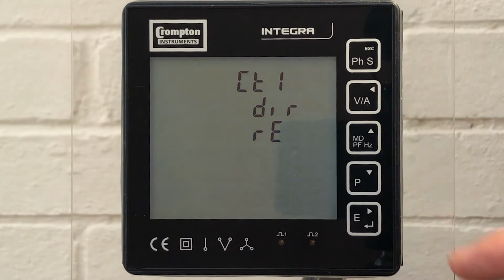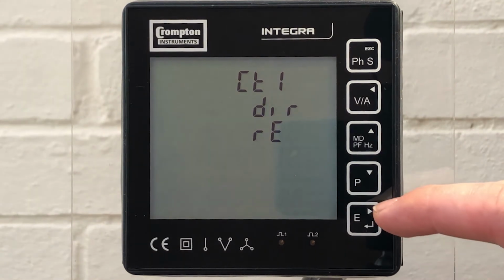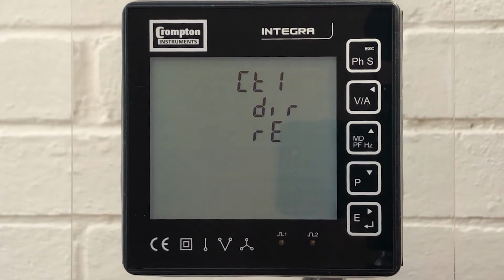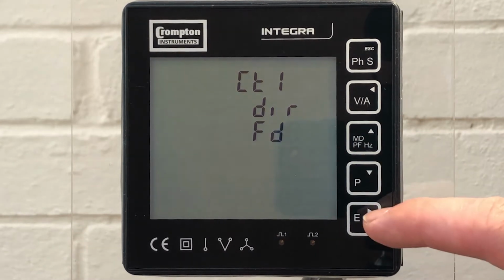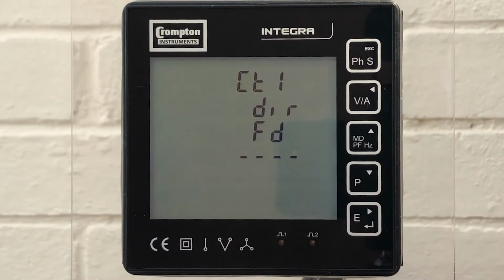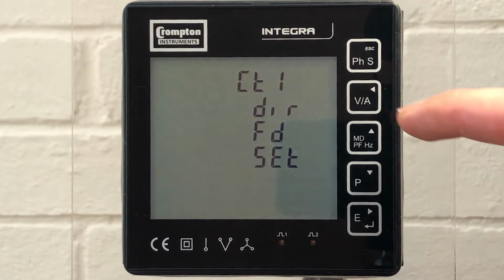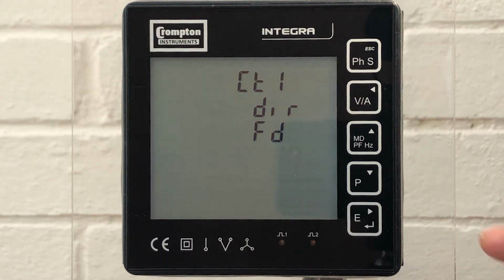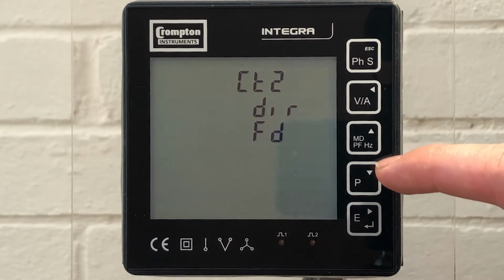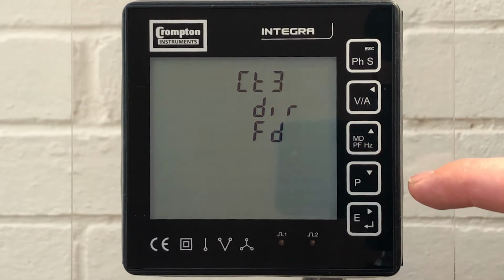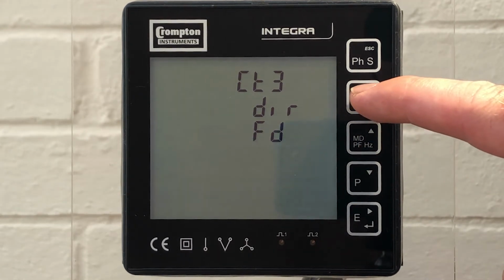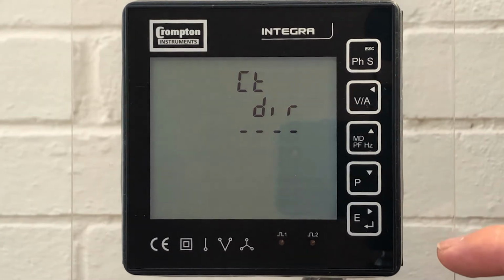If there's no wiring errors in the system, then there's no need to change this setting, but a useful feature nonetheless, especially if the CT secondary terminals have been wired the wrong way round or the input to the product itself is wired. If there are wiring errors on more than one CT, simply arrow through CT2, CT3 and make the necessary changes in the same way before pressing VA to escape.